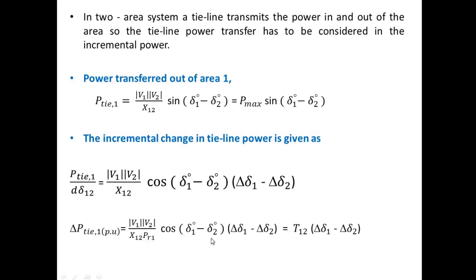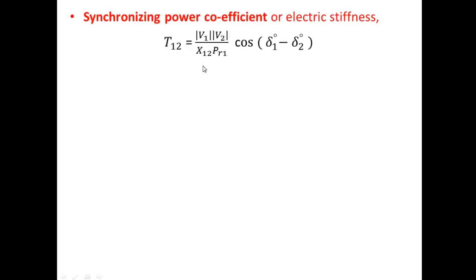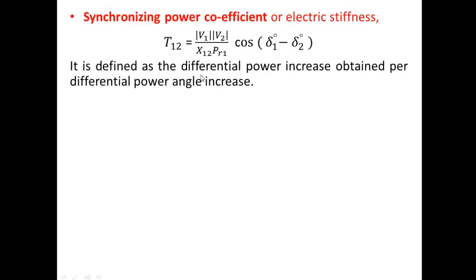The electrical stiffness T12 maintains the rigidity in the tie line power. It is defined as the differential power increase obtained per differential power angle increase — that is, the change in tie line power with respect to change in power angle. Now we need to find the relation between tie line power and frequency. We know that ω = 2πf, and we can relate ω to the rotor angle δ.